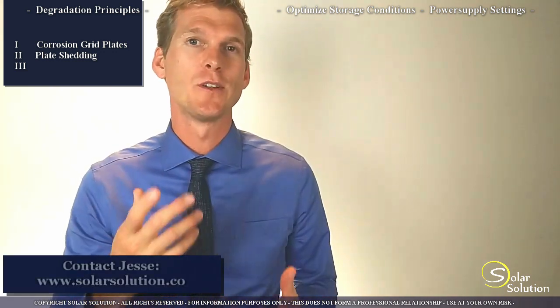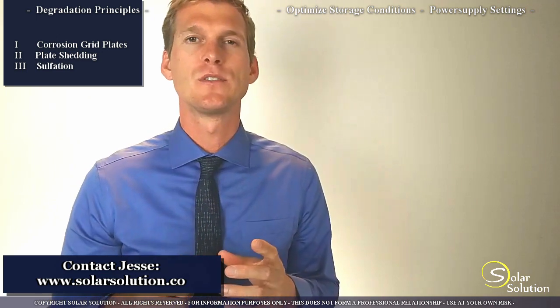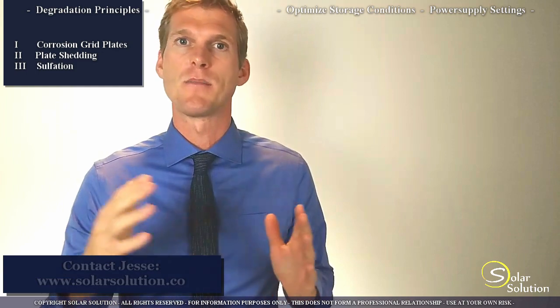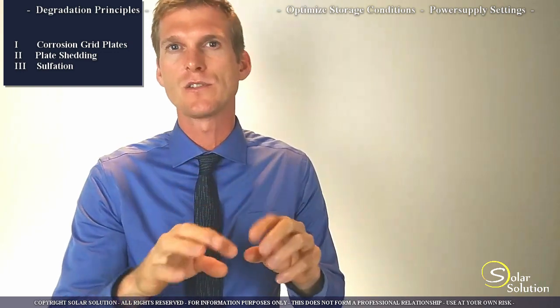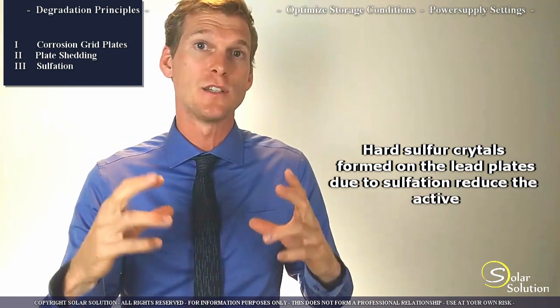So the third and the last one I want to mention is sulfation of the battery. Now this happens when a battery is partially discharged and it's left in this state of charge for an extended amount of time. Then what happens is that due to chemical reactions in the battery, hard sulfur crystals form inside of the battery. This process cannot be reversed. The result of this is lower capacity of your battery.